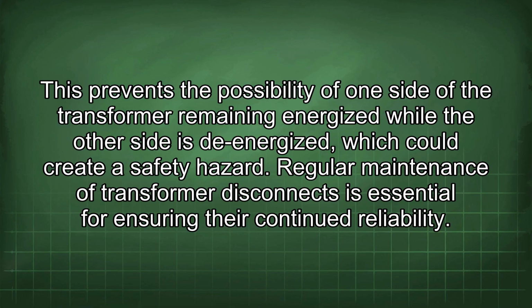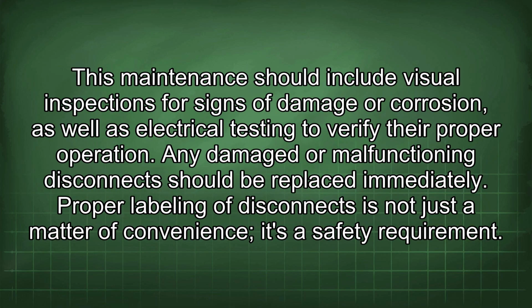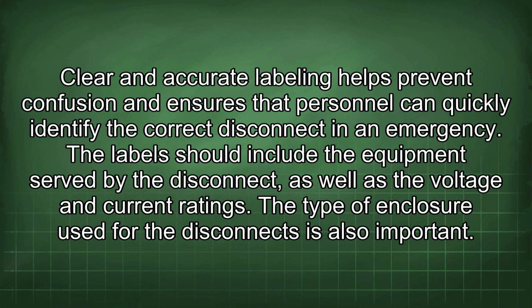Regular maintenance of transformer disconnects is essential for ensuring their continued reliability. This maintenance should include visual inspections for signs of damage or corrosion, as well as electrical testing to verify their proper operation. Any damaged or malfunctioning disconnect should be replaced immediately. Proper labeling of disconnects is not just a matter of convenience, it's a safety requirement. Clear and accurate labeling helps prevent confusion and ensures that personnel can quickly identify the correct disconnect in an emergency. The labels should include the equipment served by the disconnect, as well as the voltage and current ratings.